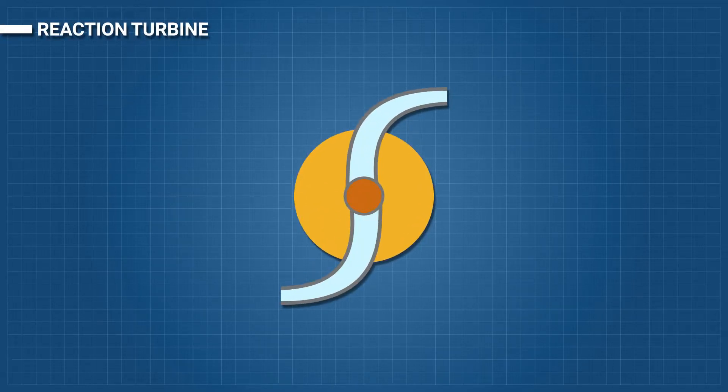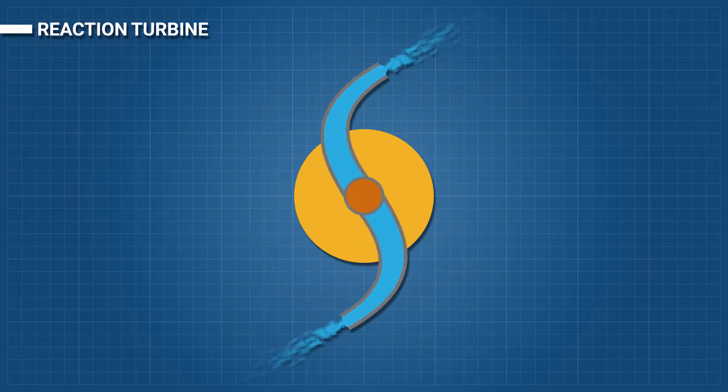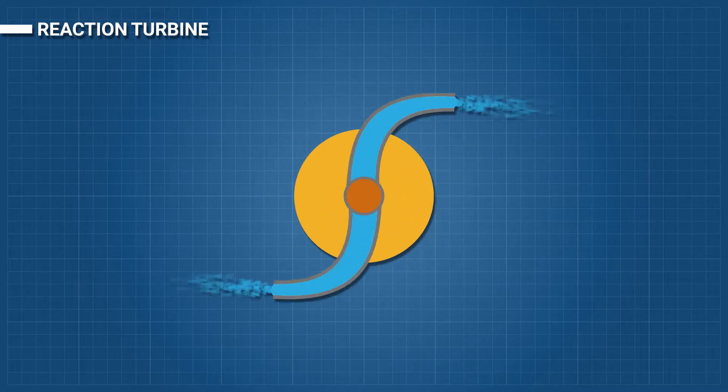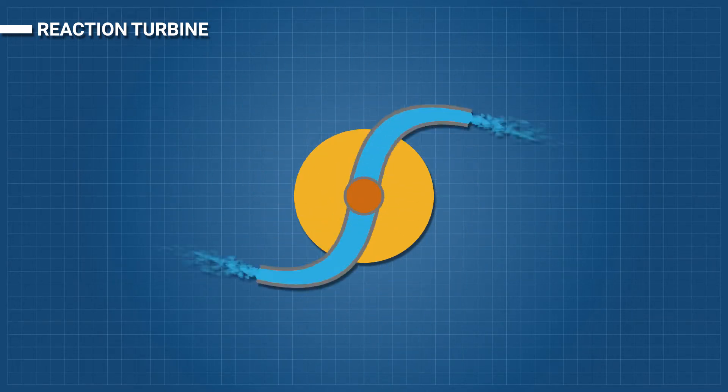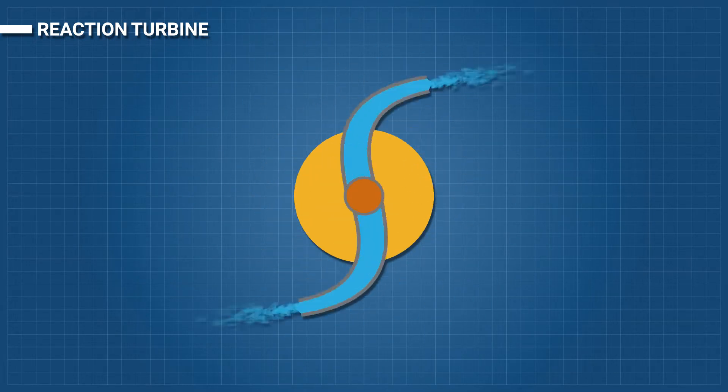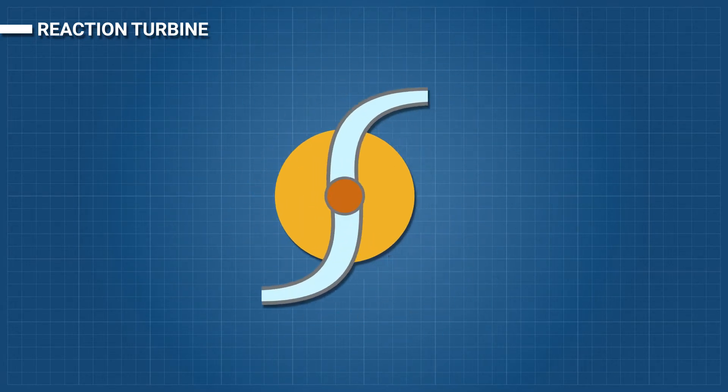A reaction turbine develops power from the combined action of pressure and moving water. The runner is placed directly in the water stream flowing over the blades rather than striking each individually. Reaction turbines are generally used for sites with lower heads and higher flows than that of impulse turbines.